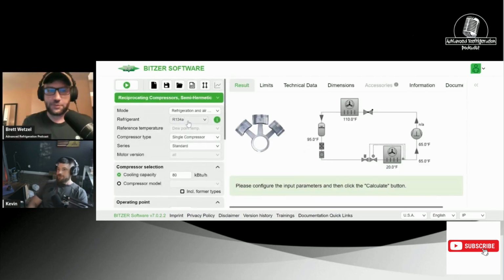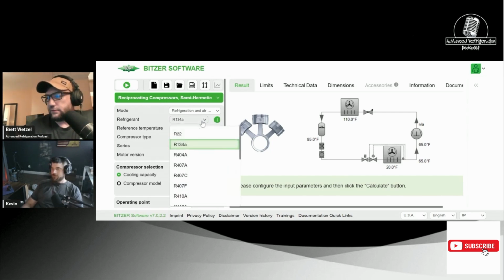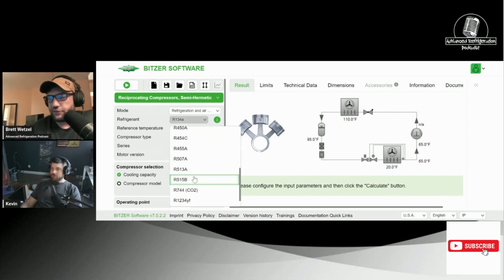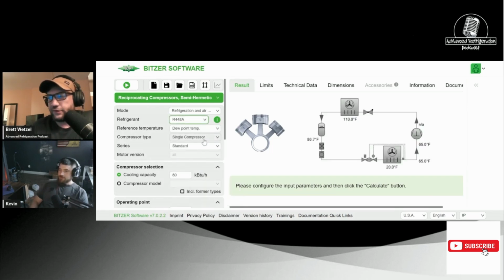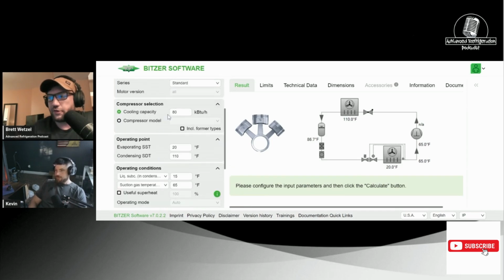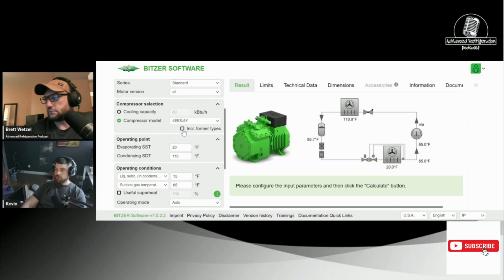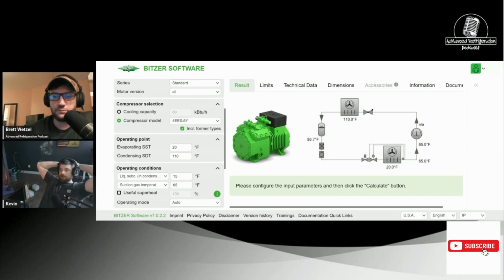Okay, now we're in American units. Anyway, are we doing other refrigerants, or the 448? 448. All right, we have 448. Single compressor. Is there a certain model number that you know of? So this is one thing, guys. If you cannot find the compressor in the Bitzer app, you need to change it from cooling capacity to compressor model. And then also include former types. If you have an older Bitzer model number that they don't make anymore, it's going to be in there. They only put the newer ones in the first drop down. So if you can't find it, it's in there.